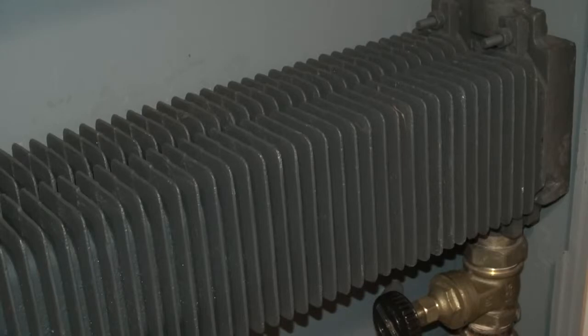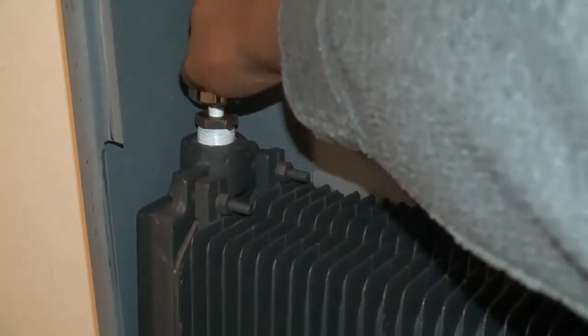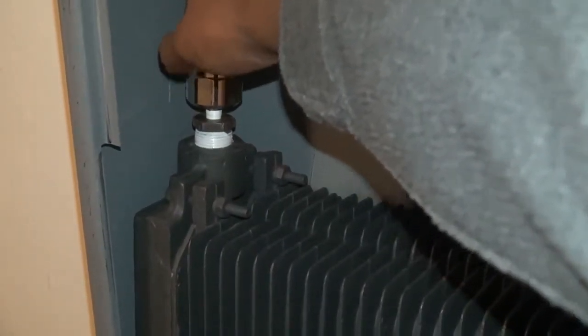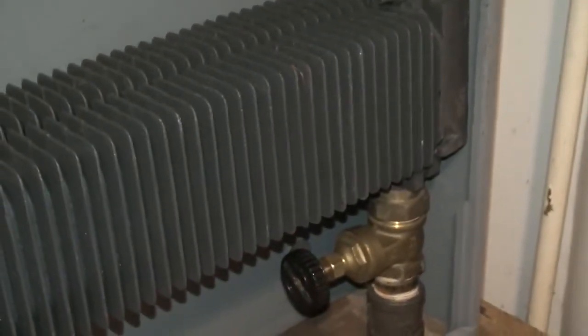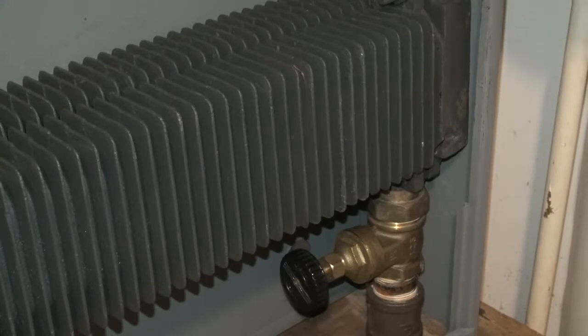The only time you start to get a reading on that gauge is when the air vents on your radiators lock out, because that causes a pressure buildup. That's when your boiler starts making pressure. On a residential grade boiler, using a 4-family or 2-family house as an example, in many cases the only time you're going to start to see steam pressure build up is if the boiler has been running consistently for at least 30 to 40 minutes. And that's on a residential grade.